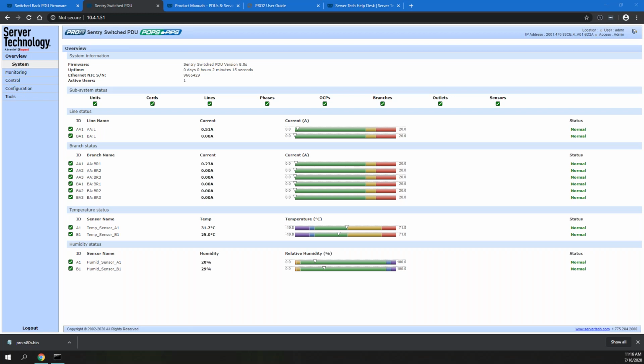If any PDU you have is running firmware older than 8.0G, you will need to regenerate new SSL certificates using the PDU. You'll need to do this in order to use HTTPS for all modern and major browsers. The reason is we changed the certificates to use a 2048-bit key and SHA-256 as the signature hash, to comply with minimum security standards.